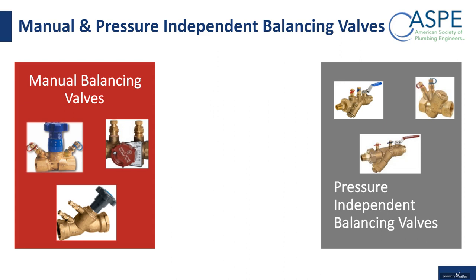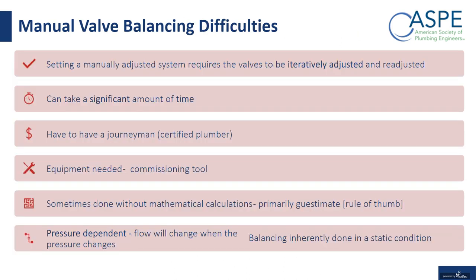And then to the right of that, in the gray, is the pressure independent balancing valves, which you notice have no knobs, but they have a cartridge that goes in them. And this cartridge you select for different flow rates. It could be a half a GPM, 3/4 GPM, 1 GPM. Some manufacturers have more granularity than others as far as the different cartridge flow rates, but that's the second type of balancing valve.